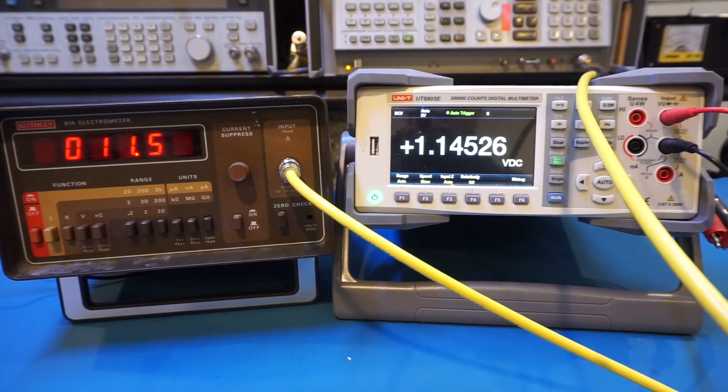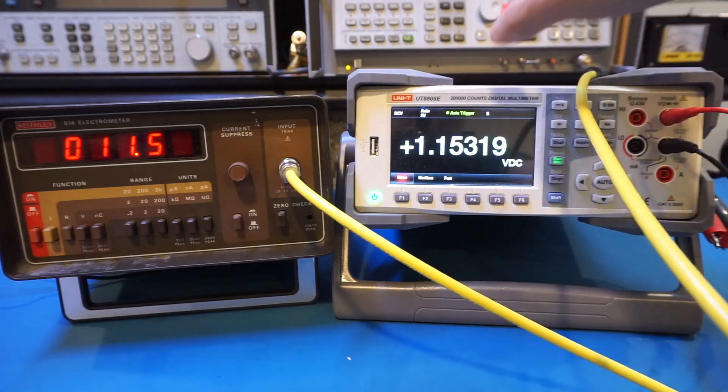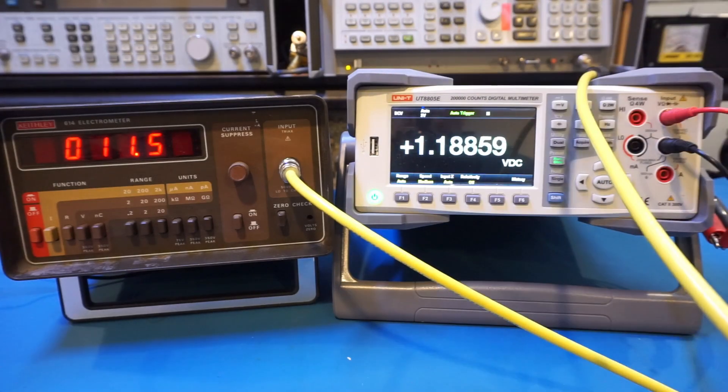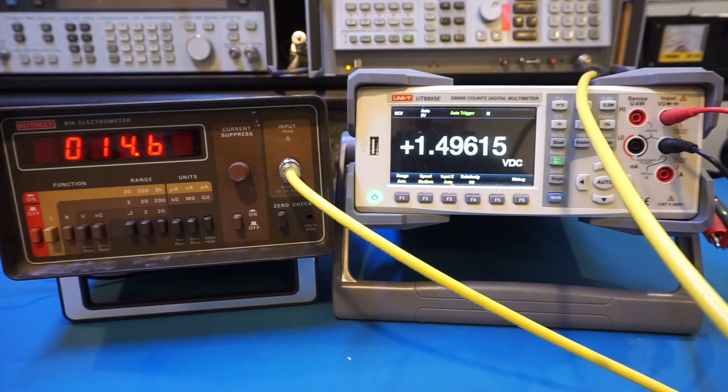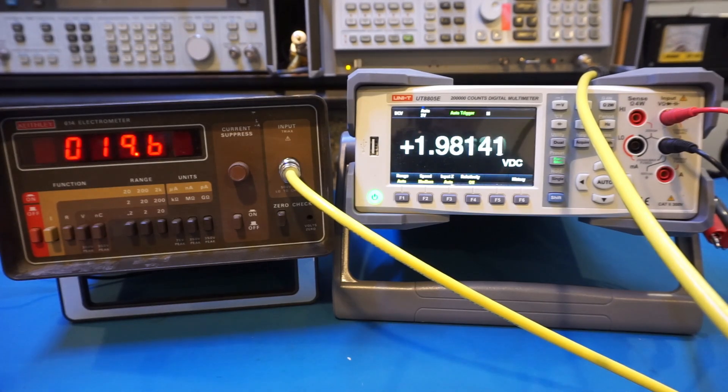And just out of curiosity, let's change the measurement update speed and see if that has any impact on the input impedance. So currently it's set at slow. Let's change it to medium. And you can see that we're actually getting higher input impedance. And by the look of it, it tops at around 20 gigaohms.